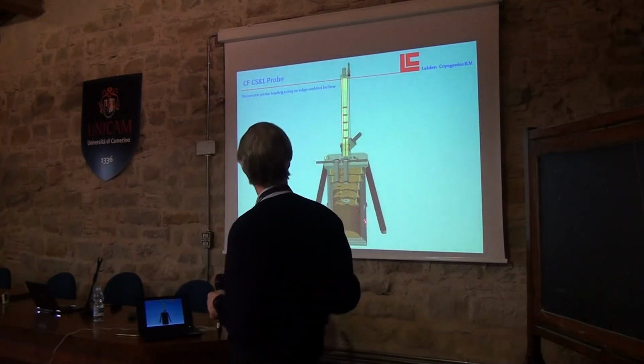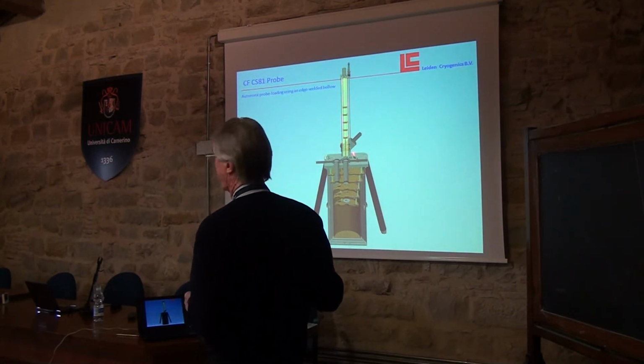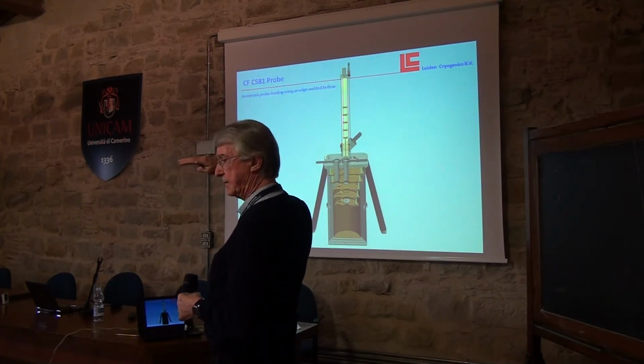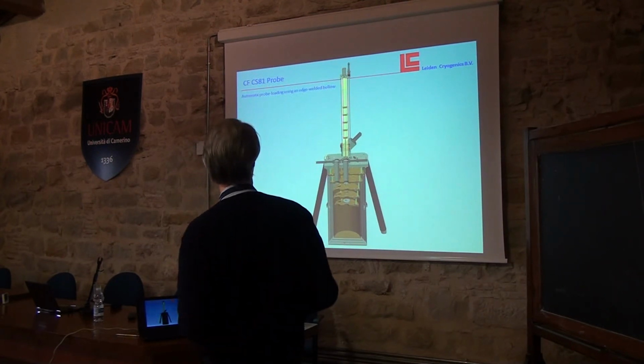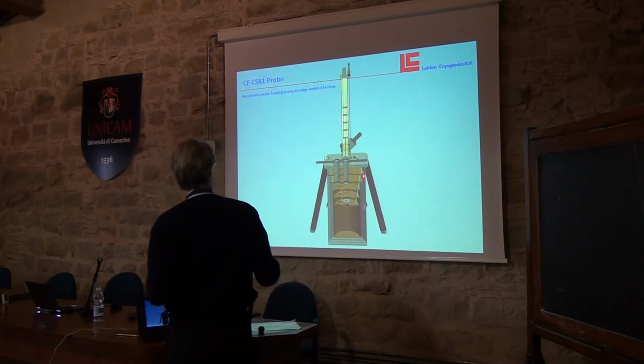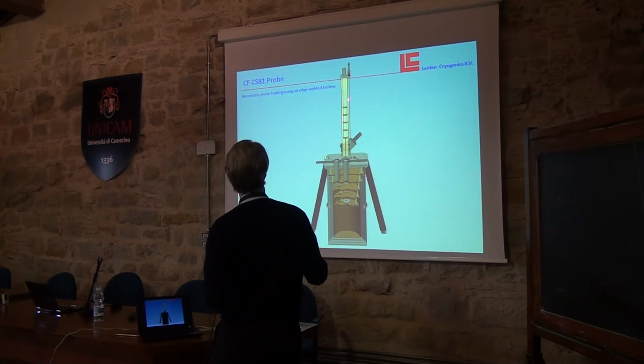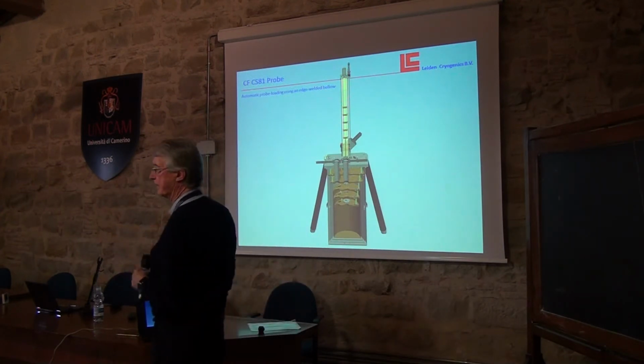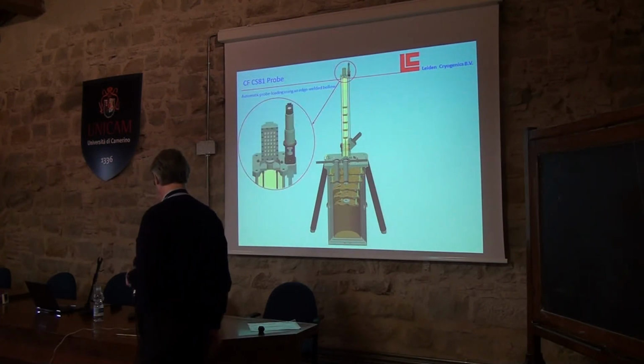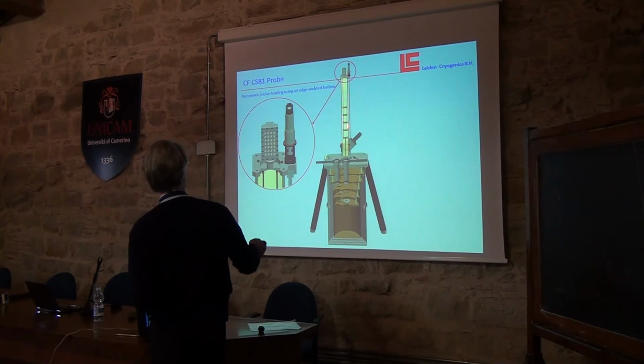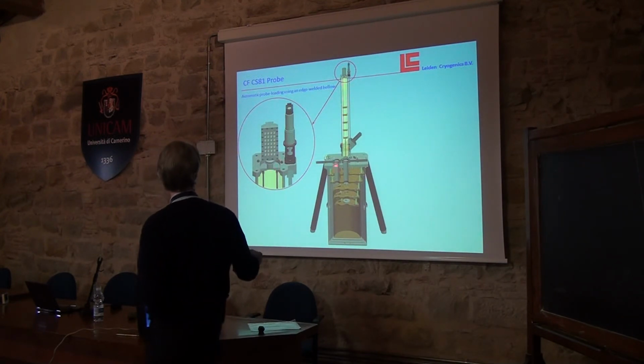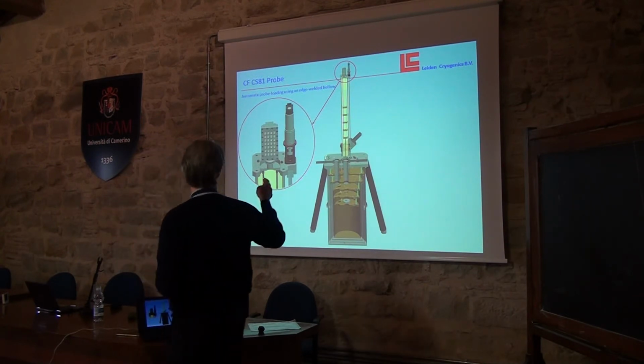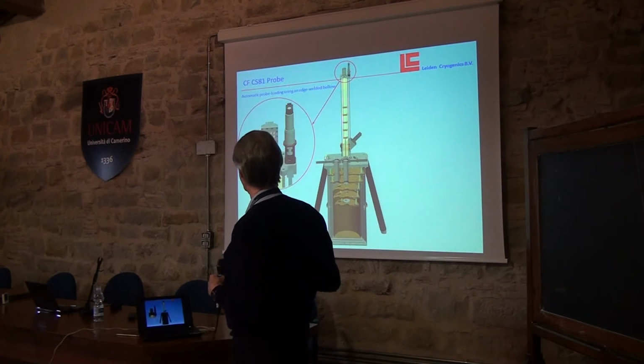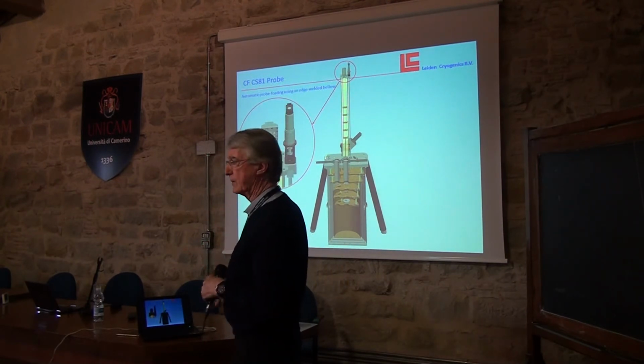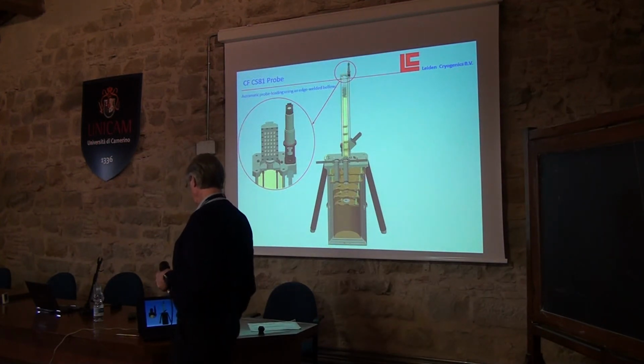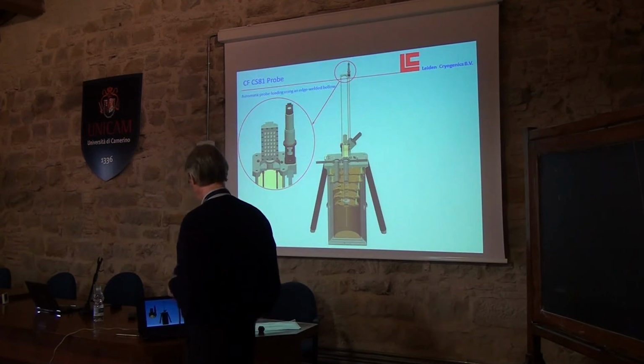This is the new refrigerator. It has a mechanical top loading probe, which has a very long bellows of 1.5 meters with more than 600 elements welded to it. It is completely mechanical, so there's a motor that lowers it, and it's programmed so that it stops at different temperatures and terminals. This is the motor, this is the spindle that drives the motor. And here you can put your probe. The probe is something that you insert on the bellows, and you can mount all your samples, whatever, then you can change them very easily. You take one, put the other, and that increases the production. So that's how it works.